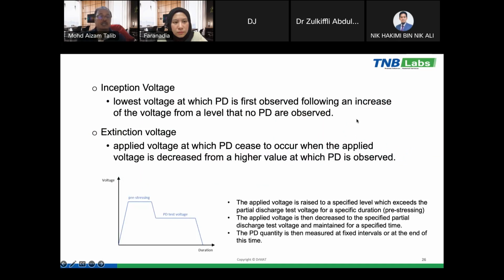The second one we can analyze in terms of inception voltage. What is the inception voltage? It is the lowest voltage at which PD is first observed when we increase the voltage from a level at which no PD is observed. For example, during the testing, we increase the voltage slowly until we see the PD pulse, and we record at what level of voltage the first PD occurs. That is called the inception voltage.